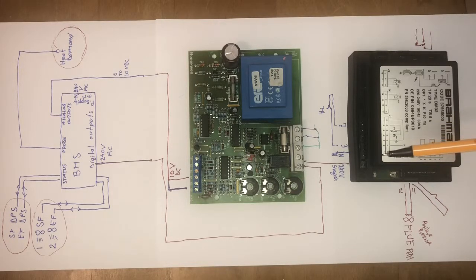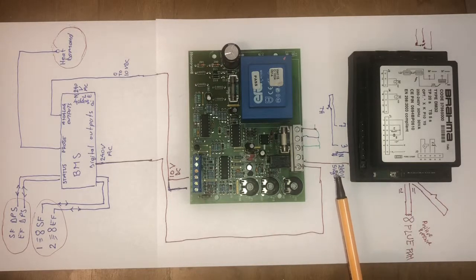This is a simple version. I just want to let you know that it is not so simple, because in between this enable signal and the controller number 1, you could have a lot of things. You could have, as an example, the high limit thermostat safety stat. You have the high limit with manual reset, the high limit with automatic reset. You can have the fire alarm. You can have a safety push button. If you use a logic gate, you can use an AND situation for multiple safety devices, and only if all of them are healthy, the system will work.